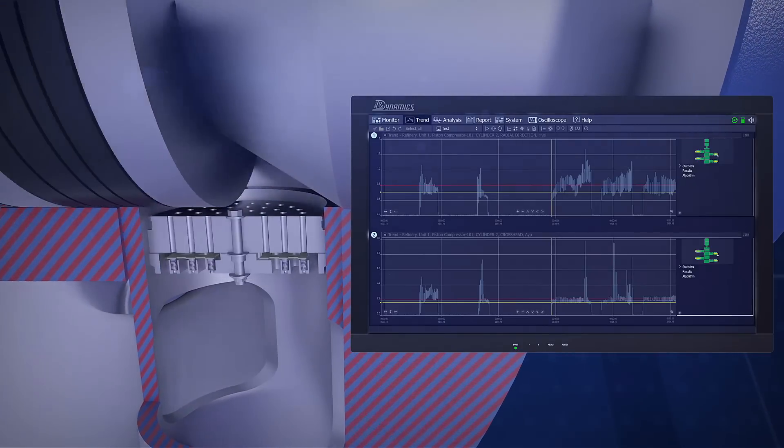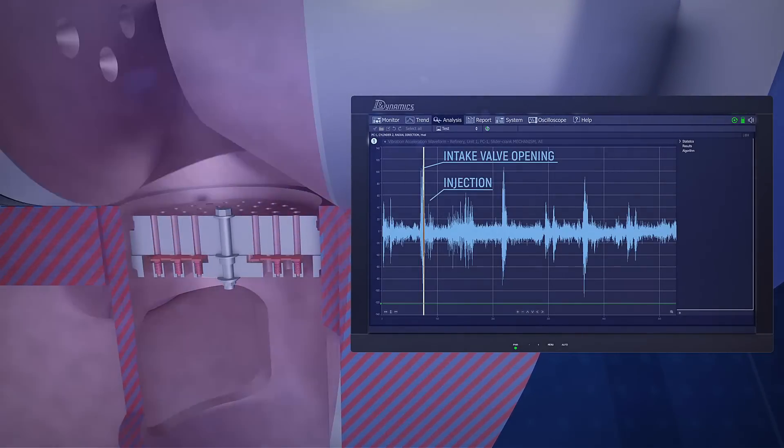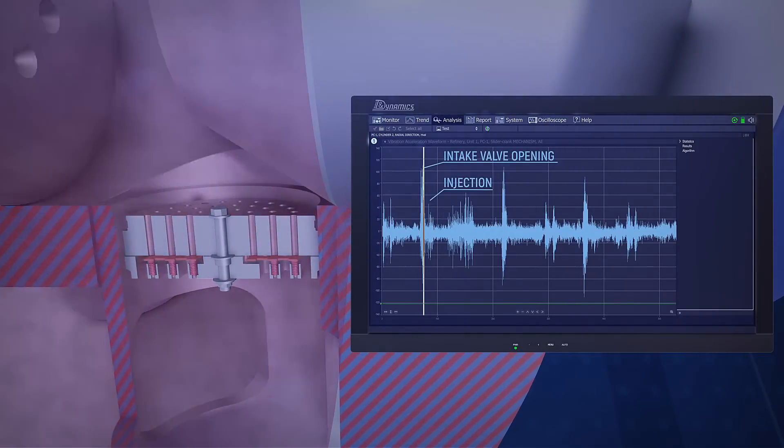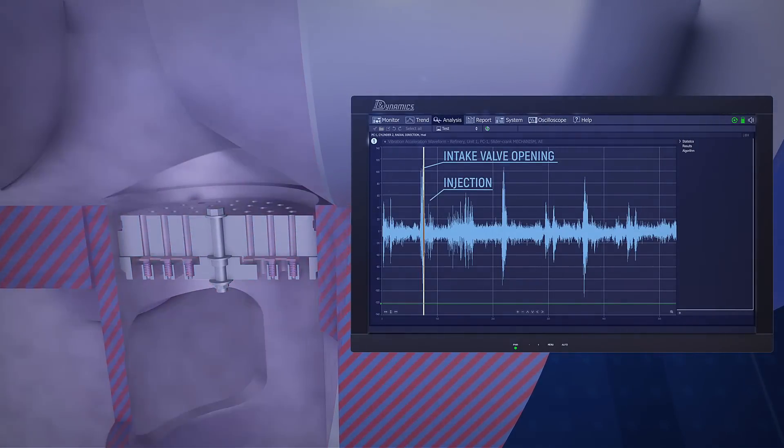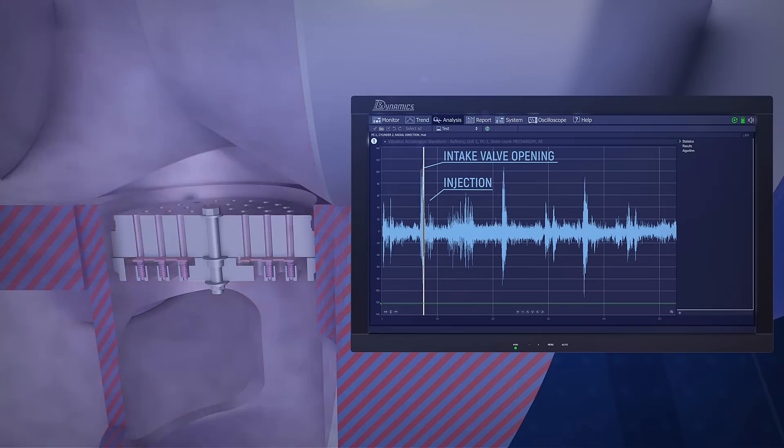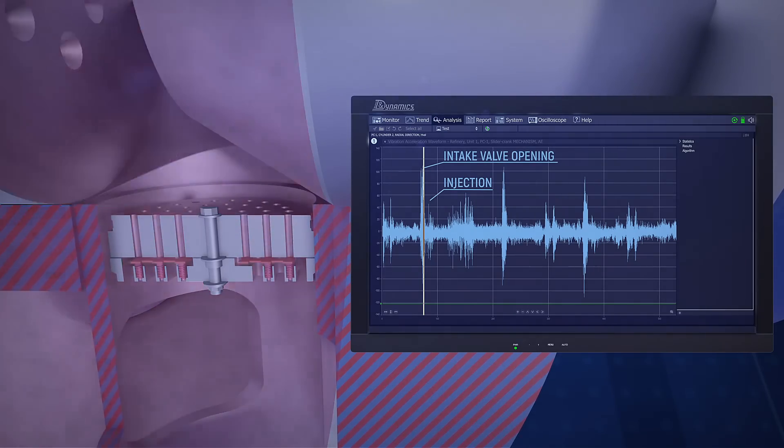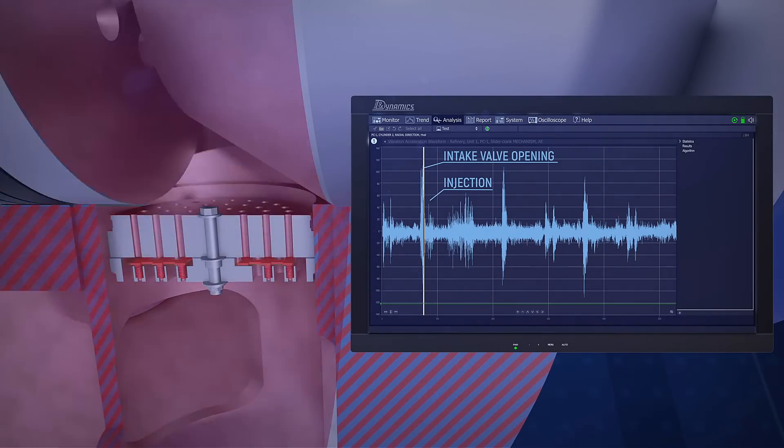When the reliability team compared the trends of valve deterioration with the trends of hydraulic shock, they confirmed the correlation. After each hydraulic shock, valves quickly deteriorated.